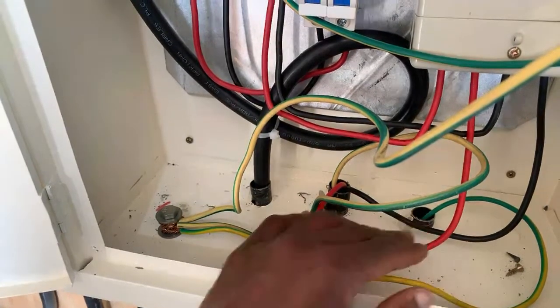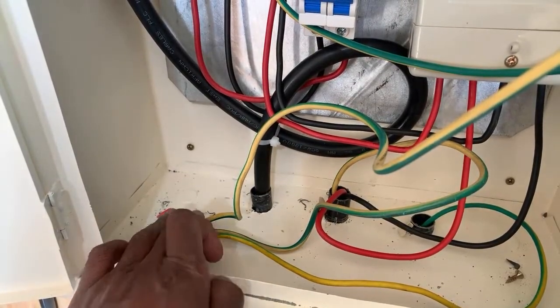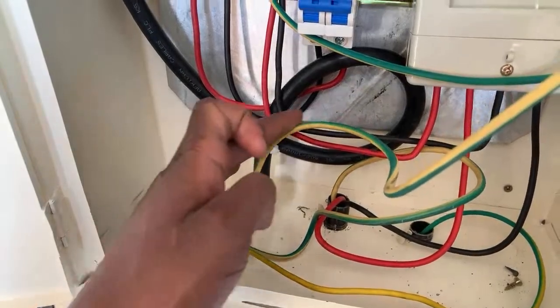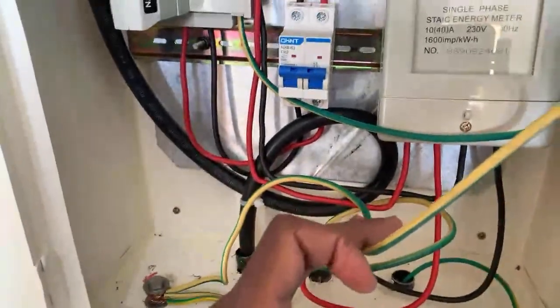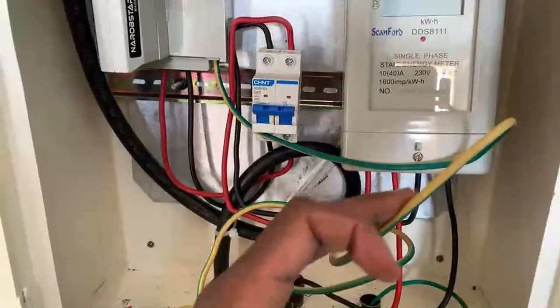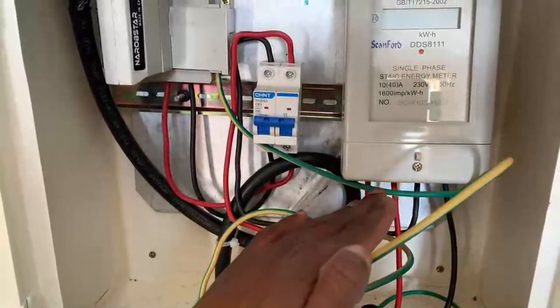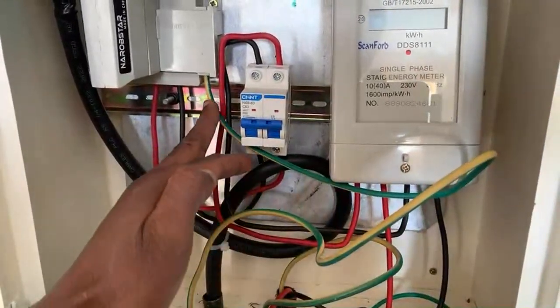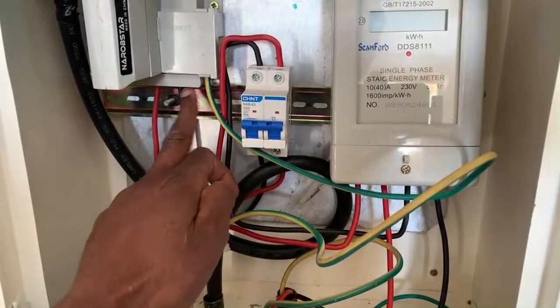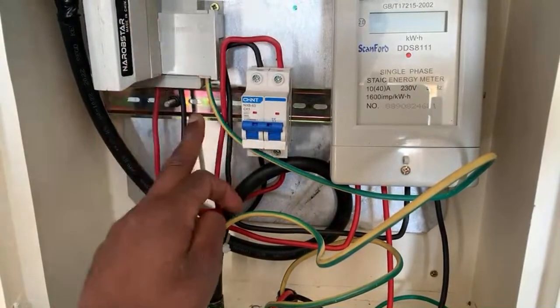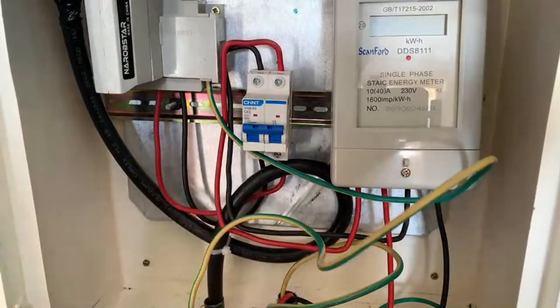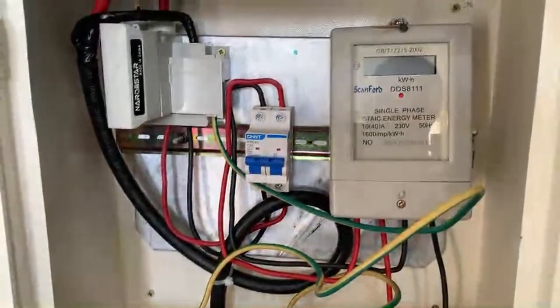If that entire connection is compromised, then these charges have another alternative route. They will flow through this cable here, according to our country's wiring, all the way to our neutral connection where we have bonded the neutral and the earth, and then go back to the source, the transformer.